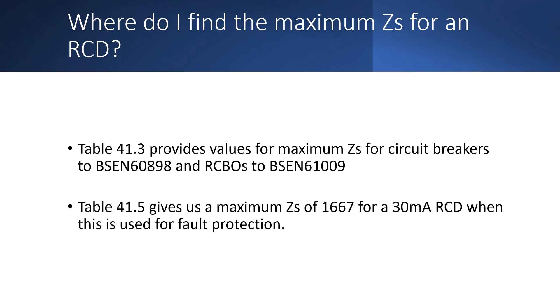If we turn over the page in BS7671 and look at table 41.5, this gives us a maximum ZS of 1667 ohms for a 30 milliamp RCD when this is used for fault protection. So if that's the case, why does table 41.3 say that the maximum ZS for a 32 amp type B RCBO to BS EN 61009 is 1.37 ohms?